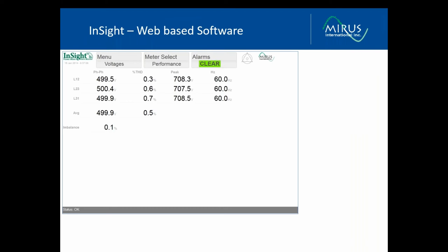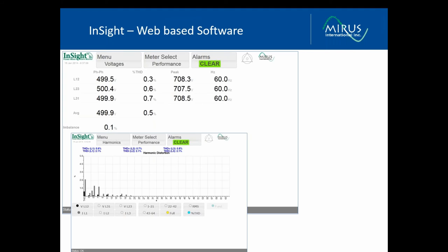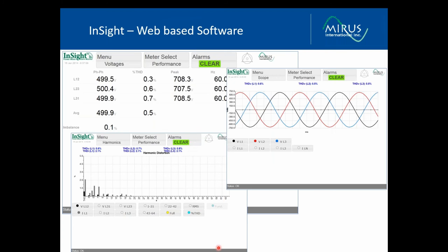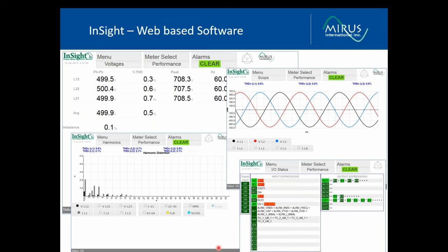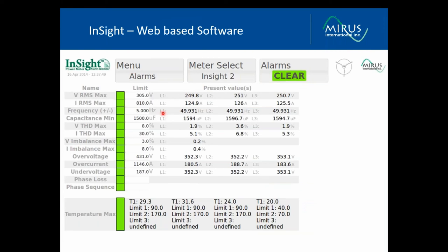The monitoring system is a web-based software system. There's a lot of information that can be presented through a connection through the internet and/or a local display. This particular one shows the voltage measurements. We can also do current spectrums. We measure all the way up to the 63rd harmonic. We have the waveforms, voltage and current waveforms, and there are alarms that can be configured as part of the metering package.